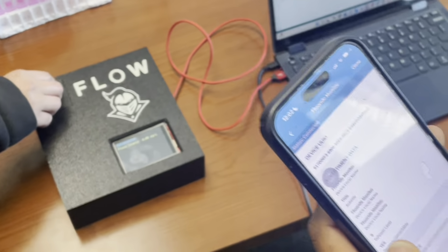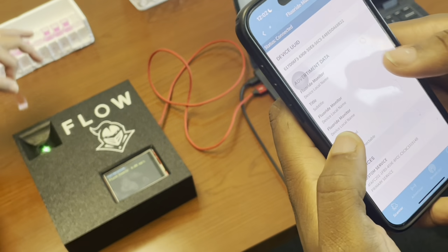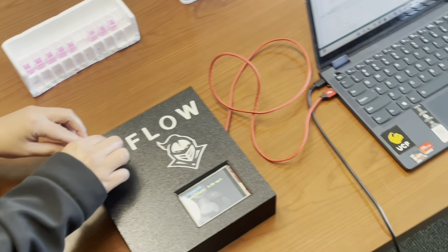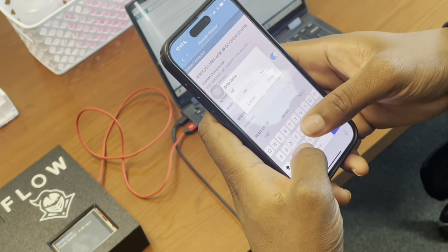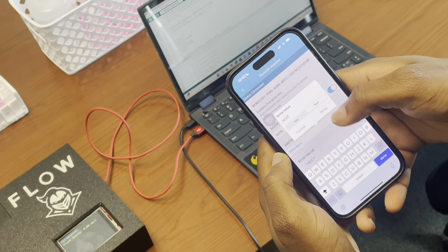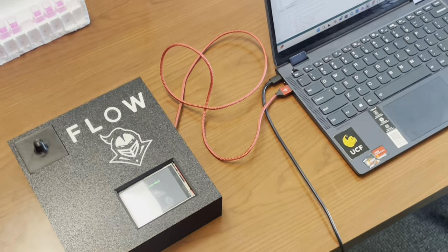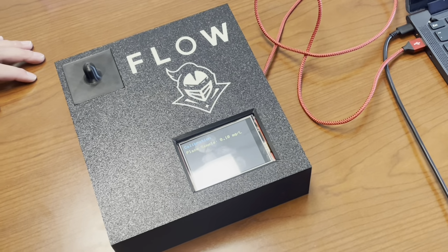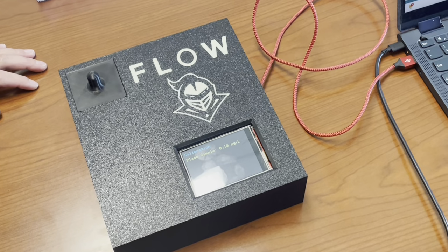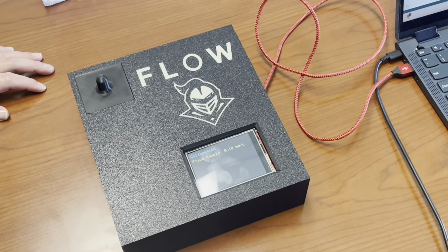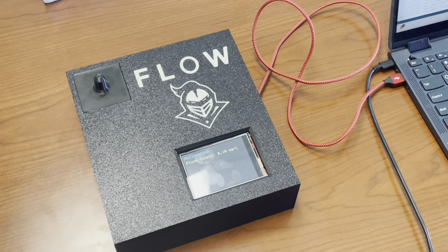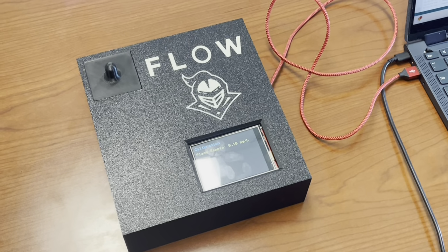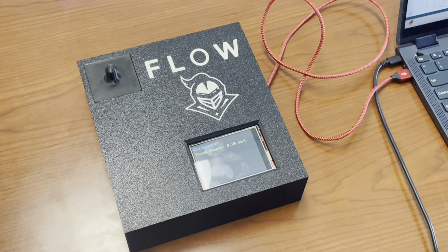All right, so once we connect through the app, Alyssa's going to place the sample in here, and from here we'll just do a command, which is next, and it will record it. Now on the display, it's still in our calibration phase, we have our sample, and it'll store and record the values through our BLE connector app. And now it says place sample 0.10, which now we will place.